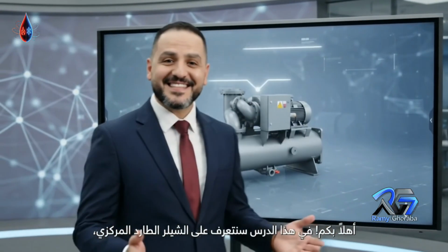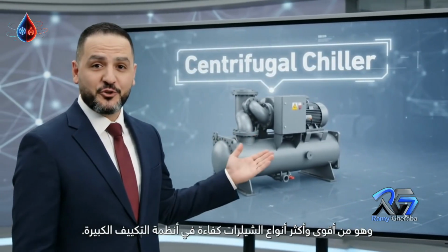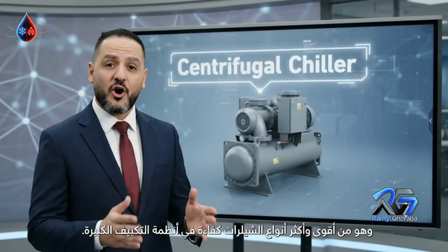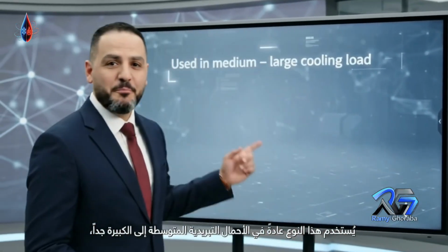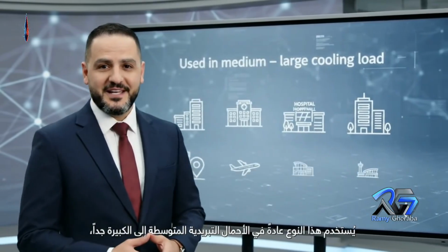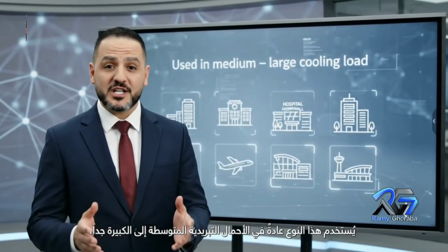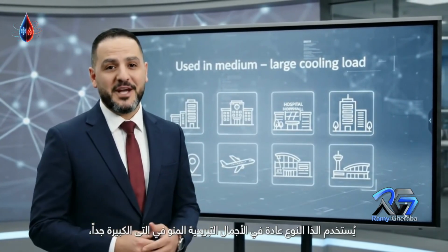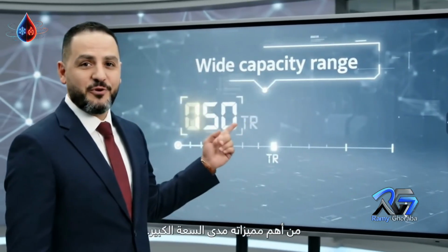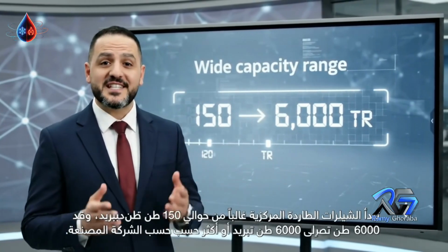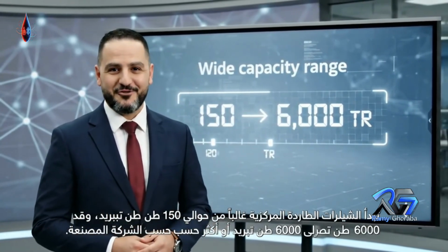Welcome! In this lesson, we're exploring the centrifugal chiller. It is one of the most powerful and efficient chillers used in large HVAC systems. This type of chiller is typically used for medium to very large cooling loads. This makes it ideal for towers, hospitals, malls, airports, and major facilities. One big advantage is its wide capacity range. Centrifugal chillers commonly start around 150 TRs and can reach 6,000 or even more, depending on the manufacturer.